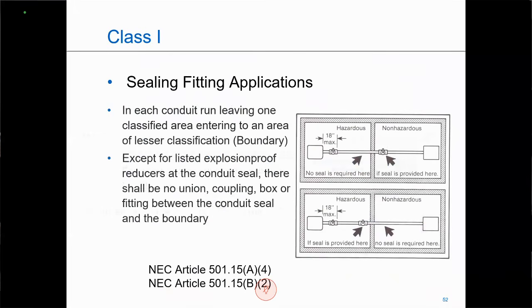Now, when it comes to boundary seals, here we're making sure that the gas does not migrate from one classified area to a lesser classified area. So my boundary seal can be on either side of the boundary, but must be within 10 feet of the boundary. And once I put in that boundary seal between the boundary and that sealing fitting, I can have no other fittings, any types of couplings, except for a listed reducing bushing used on the boundary seal.